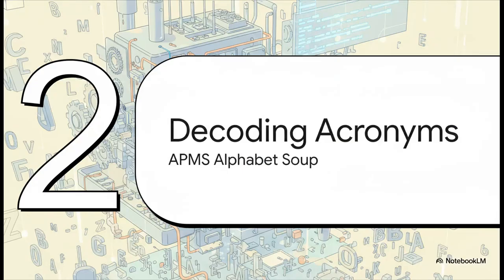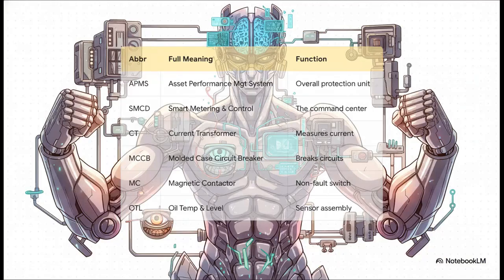Moving on to Section 2, Decoding APMS Alphabet Soup. Okay, before we crack open the machine itself, we really need to decode the, let's be honest, incredibly heavy technical jargon here. Consider this your ultimate cheat sheet. In engineering docs like this, it is so easy to get totally buried in acronyms, right? But matching them to their real-world jobs clears things right up. APMS is the whole unit, the Asset Performance Management System. The SMCD is our command center, or the brain. The CT, or current transformer, and the OTL, which is oil temperature and level, act as our senses. And the MCCB, the molded case circuit breaker, alongside the MC, the magnetic contactor, those are our muscle. Keep these tucked in your back pocket because they are the core building blocks for the rest of this explainer.